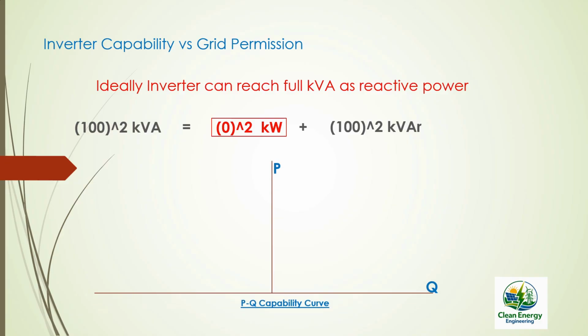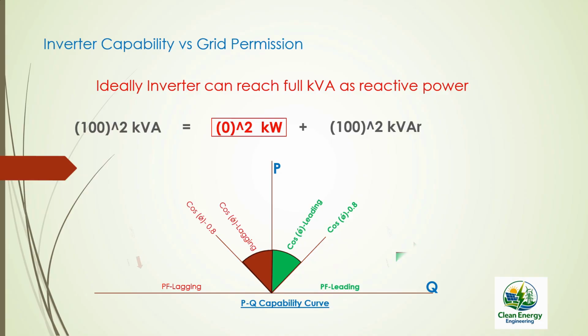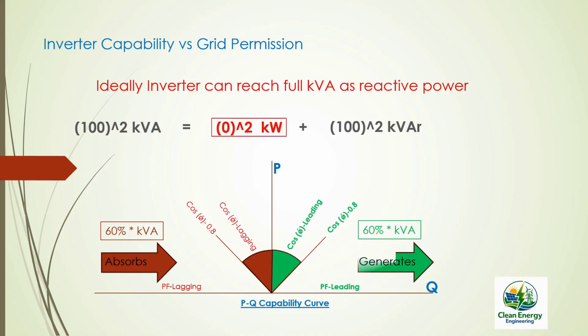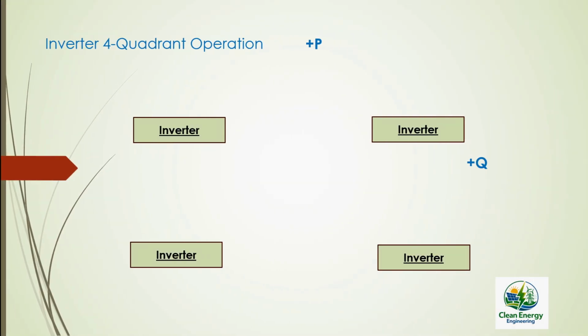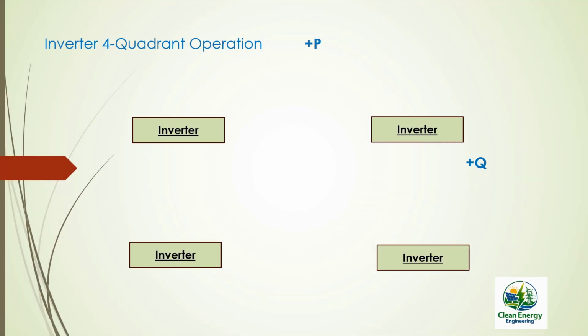PQ capability curve shows P on the y-axis, Q on the x-axis. Left hand shows lagging power factor mode, right hand shows leading power factor mode. PQ capability curve shows the range of power factor 0.8 lagging to 0.8 leading. In lagging mode, inverter absorbs reactive power. In leading mode, inverter generates reactive power. With a calculation, you will find the inverter can generate or absorb a maximum of 60% of its kVA rating as reactive power at 0.8 power factor.